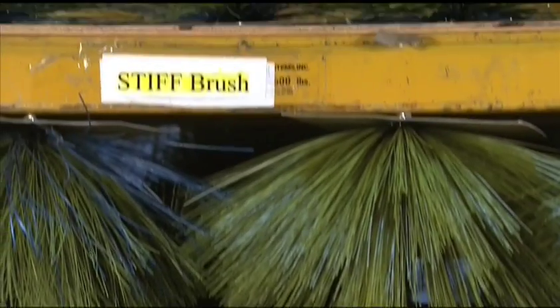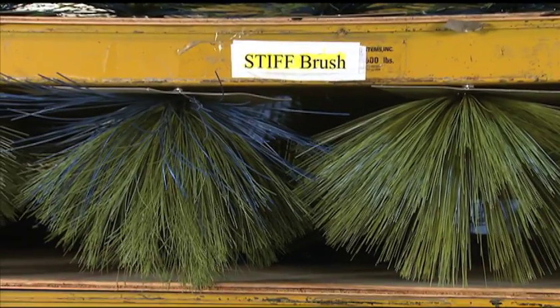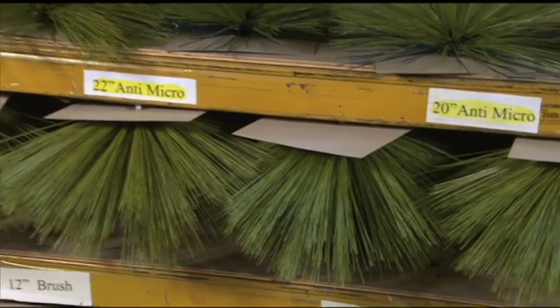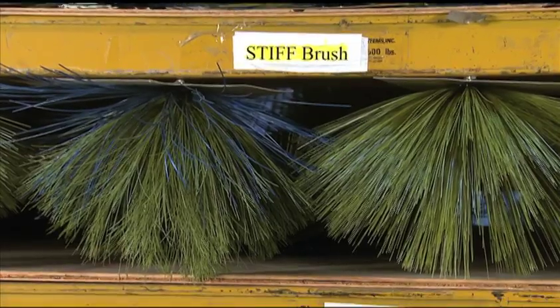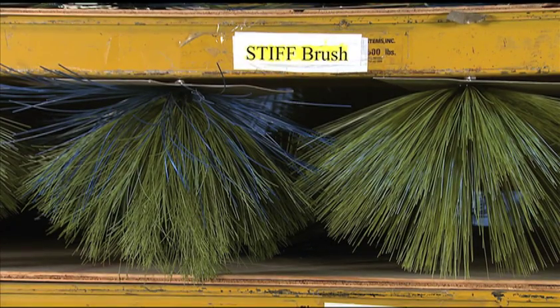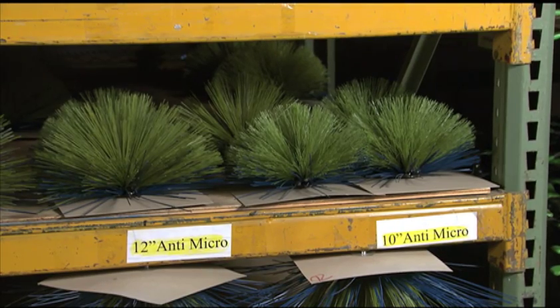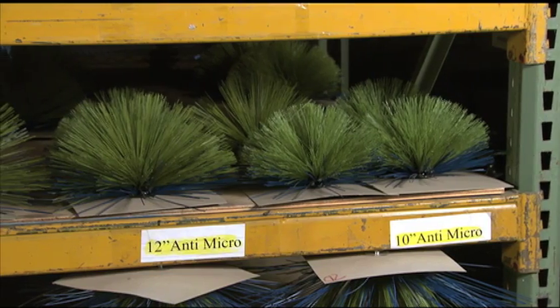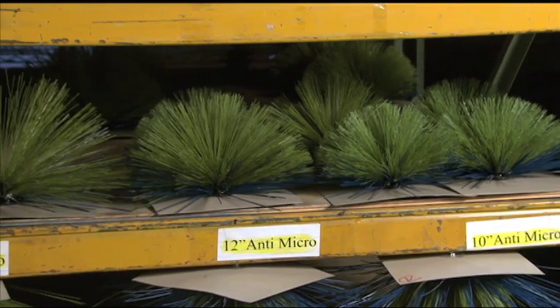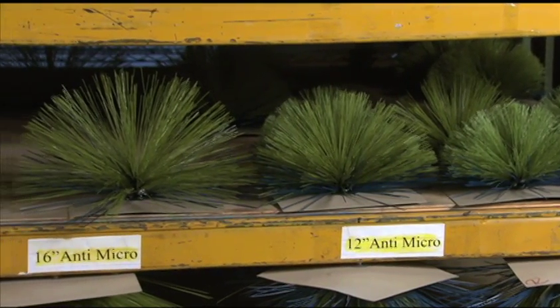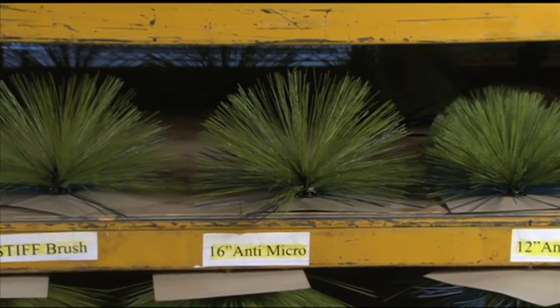Then we have your stiff bristle brushes, which have the blue and green bristle, and your soft brushes only have green bristles. The stiff bristle brush is used for aggressive cleaning applications and sheet metal ducting only. It's not to be used in flex duct, duct board, or duct liner. Your standard bristle brushes can be used in all of those applications, and typically what you're going to be doing is looking for a 2 to 4 inch increase in size of the horizontal height of the duct.